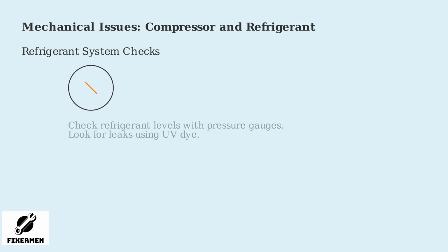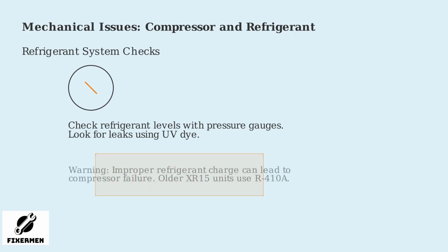For refrigerant-related issues, use pressure gauges to measure system pressure. Low levels indicate leaks or improper charging. UV dye helps visualize leaks under blacklight. Important warning: an incorrect refrigerant charge puts excessive strain on the compressor, potentially causing permanent damage. Note that older XR15 models use R410A refrigerant, which requires specific handling procedures.